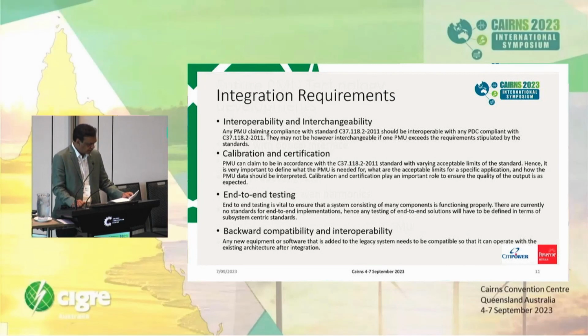So, firstly, there are so many manufacturers of PMUs. It is very important for them to be interoperable, so that if required, one PMU can be replaced with another PMU of a different manufacturer. Ideally, all PMUs complying to C37.118 should be interoperable, but in practical experience, we see that we always face some sort of challenges.